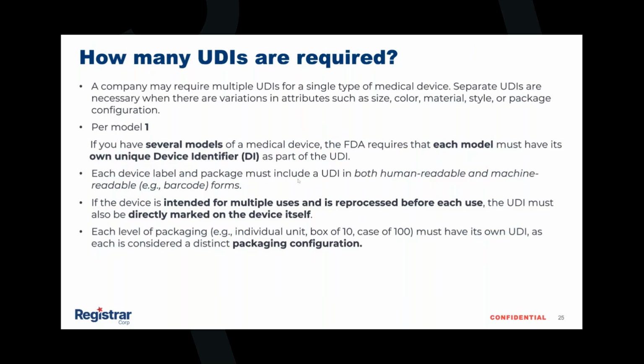Each device label and package must include a UDI in both human readable and machine readable form. If the device is intended for multiple uses and is reprocessed before each use, as mentioned again, it is required to have a direct marking on itself. Okay. The UDI is required on each level of packaging, which is the individual and the boxes, which again, those are the higher packaging levels.